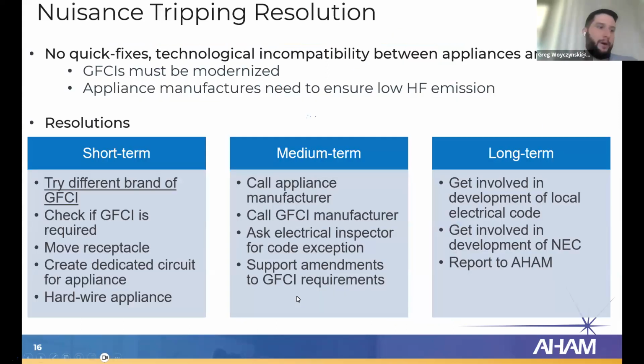All right, most important part, nuisance tripping resolution. How can you all fix nuisance tripping when it happens? So unfortunately, there's no quick fixes. There is a technological incompatibility between appliances and GFCIs right now. GFCIs need to be modernized. And there's also a role appliance manufacturers can play in making sure that they don't have that high frequency noise and making sure that that high frequency noise is safe.